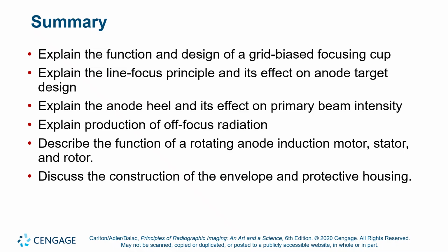The line focus principle is based on the principles of trigonometry, such that the small side of the triangle can remain small, but the hypotenuse can absorb the bombardments and can be the bombardment surface for the electrons. And so with a target angle, usually the target angles range, think small is like 5 degrees all the way up to 20 degrees. With a target angle, you can spread out electron bombardments over the hypotenuse of the triangle, while effectively the X-rays appear like they're the small side of the triangle, that is the opposite side of the triangle.